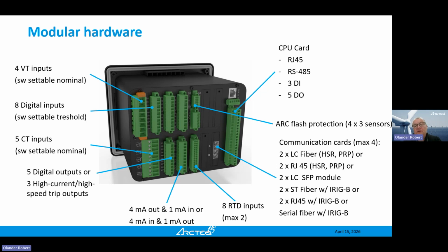But that is depending on the type of the device. And then depending on the type, you will have a certain amount of open slots. The current will take 2 slots, the voltage will take 1 slot. So it means that basically you have 11 slots open for any type of option that you need. Like I said, RTD, milliampere, digital outputs, inputs.